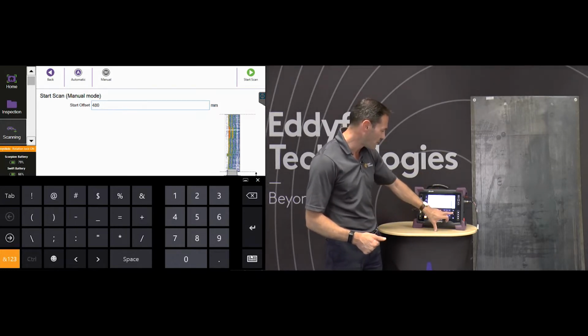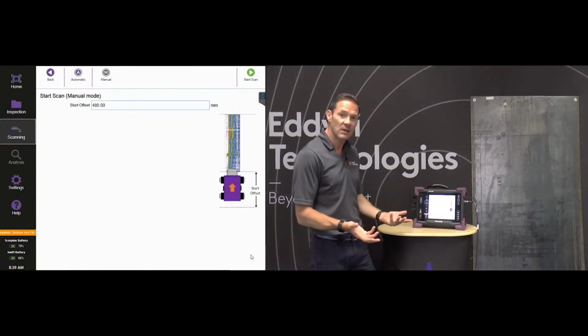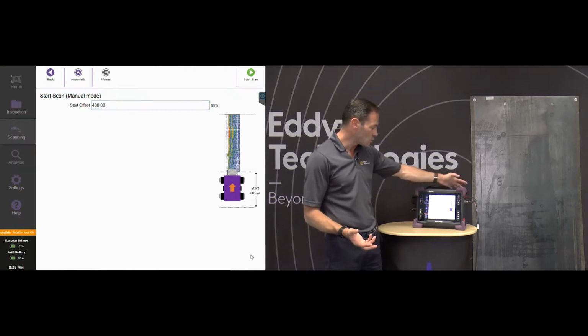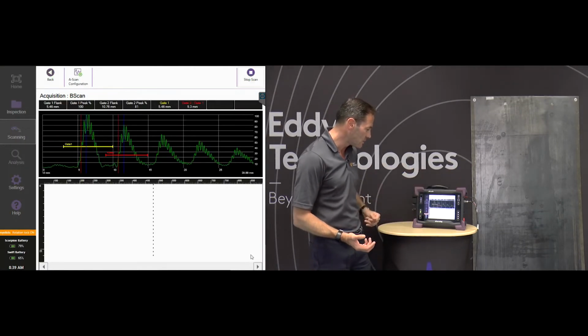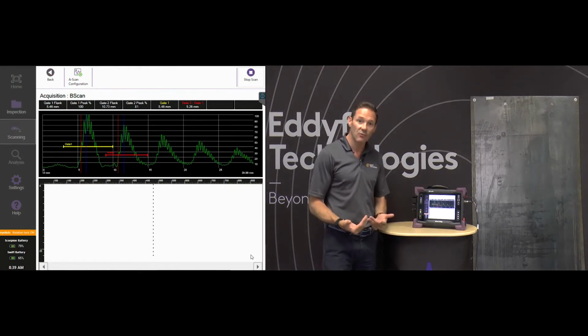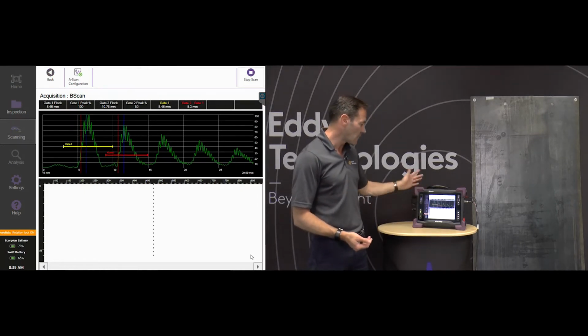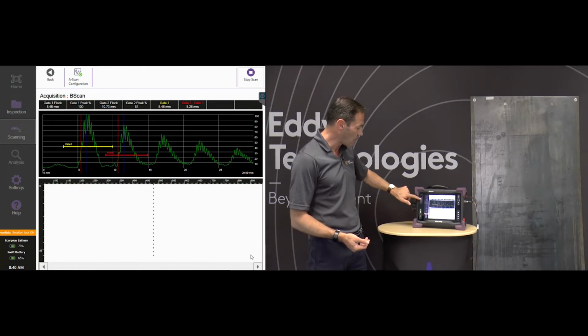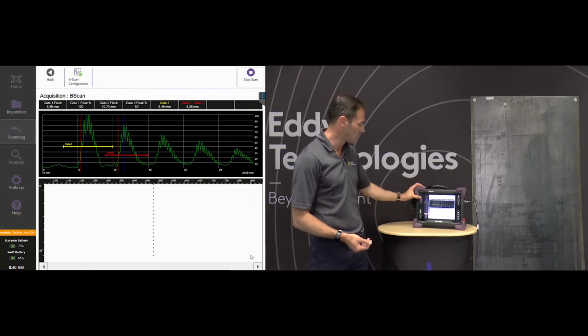So I know this is the 480 millimeters, and now I'm set to start my measurement. I click start measurement, and the system is now waiting for me to do the measurement. I have two options: using the hard buttons for forward, reverse, stop, or the joystick. In this case I'm going to use the joystick.